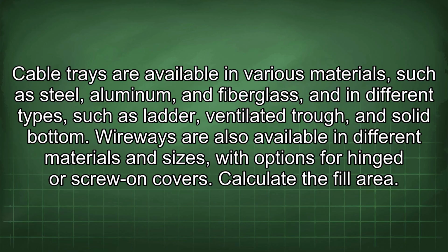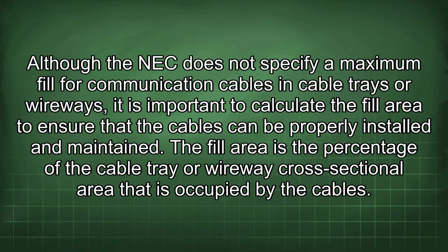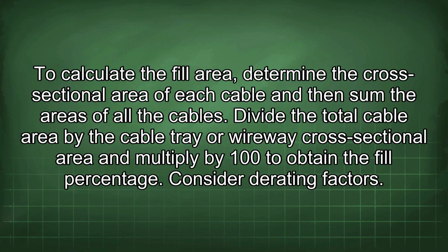Calculate the fill area. Although the NEC does not specify a maximum fill for communication cables in cable trays or wireways, it is important to calculate the fill area to ensure that the cables can be properly installed and maintained. The fill area is the percentage of the cable tray or wireway cross-sectional area that is occupied by the cables. To calculate the fill area, determine the cross-sectional area of each cable and then sum the areas of all the cables. Divide the total cable area by the cable tray or wireway cross-sectional area and multiply by 100 to obtain the fill percentage.